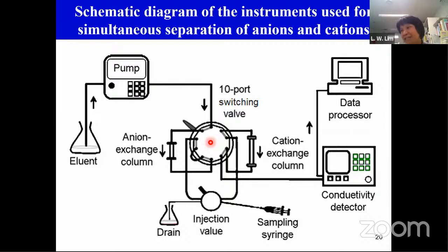Before that, it was popular, like how to do the switching and the timing of the sample injection. It's not so difficult, but you need some technique to do the switching. Once the switching is not correct, sometimes your sample will go to the drain, not to the column. It's a bit tricky, but if you are familiar with the system, maybe you can know something like this.